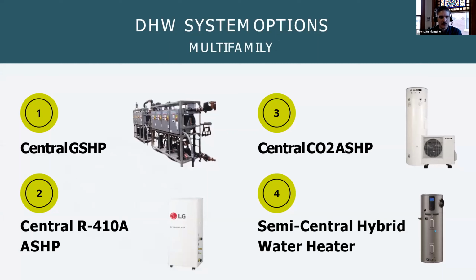So we looked at 4 different systems for this project. The first one was a central ground source heat pump system. We were driving a lot of piles for this project, so we figured we might as well look at using a geothermal system. The cost came out way too high for this project, and we ended up going away from it. The second one is a central R410A air source heat pump. And this was being designed in 2018, and the technologies just weren't really around. LG didn't have a hydro kit that could produce hot water, or our target hot water at that time. There were a couple other systems that were really just reverse chillers, and the manufacturer said, yes, we could produce hot water at 130 degrees, but that producing even at that temperature would cause premature burnout of the compressors. We decided that the technology just wasn't really there at the time, so we decided against it.